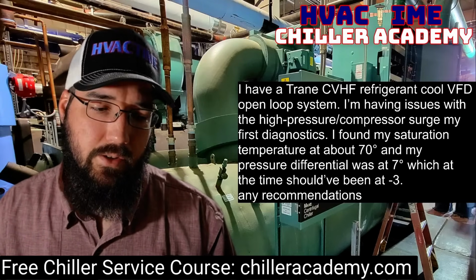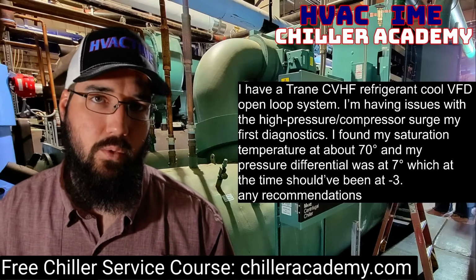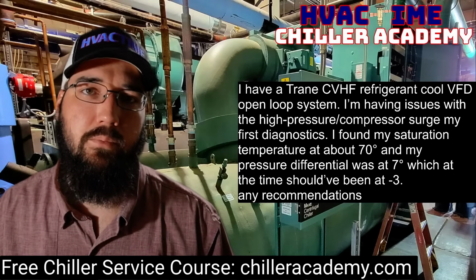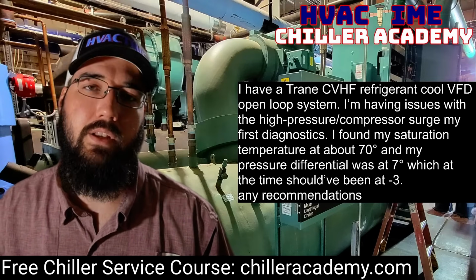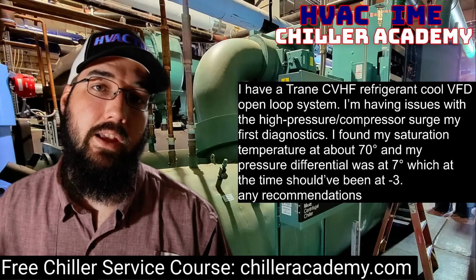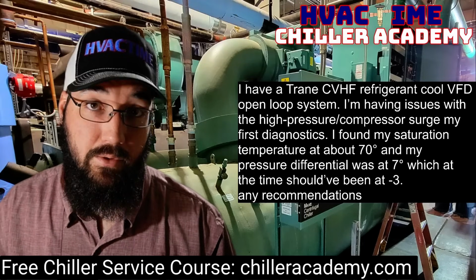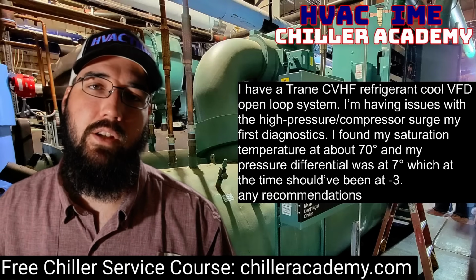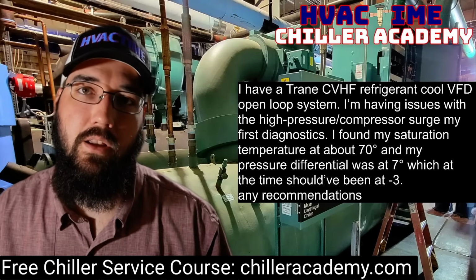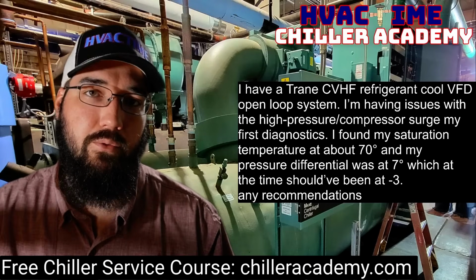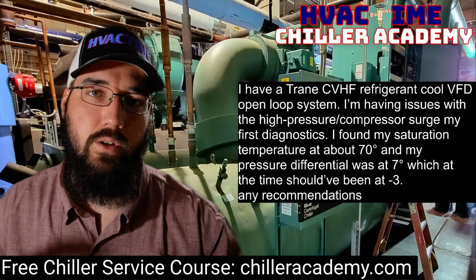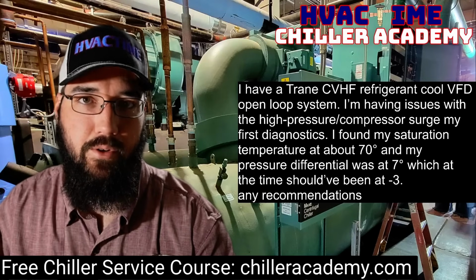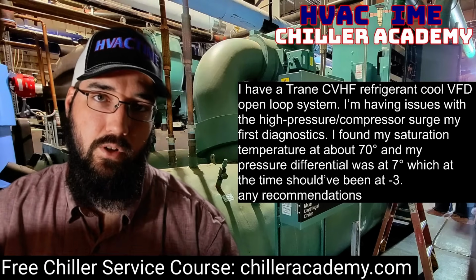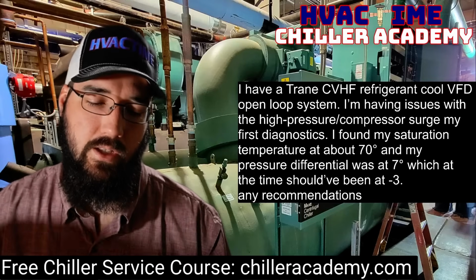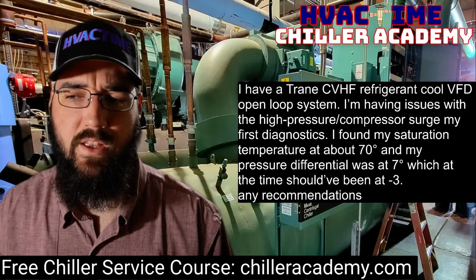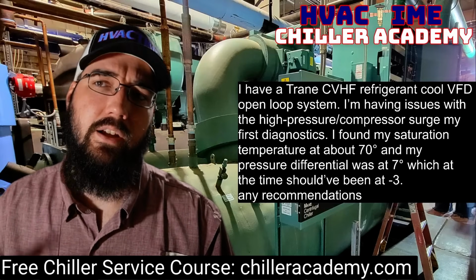Have we verified that the purge filter is actually working as well? That's going to help draw the moisture specifically out of it. But what I've actually seen, if they don't get changed routinely, maybe yours has, is that they can start to plug up and you'll start running really high liquid levels inside of your non-condensables evaporator chamber. Like your liquid levels will start rising. There's a little sight glass there. You'll see those levels start getting high in there. That could be a symptom of that filter dryer getting stopped up.